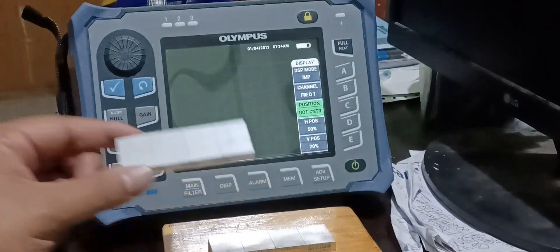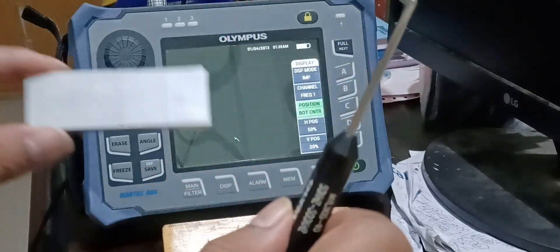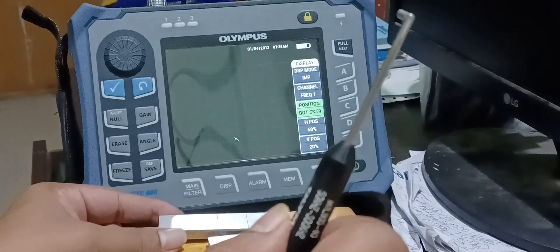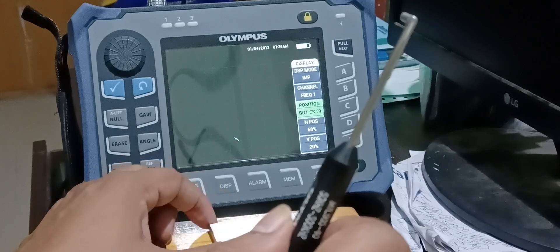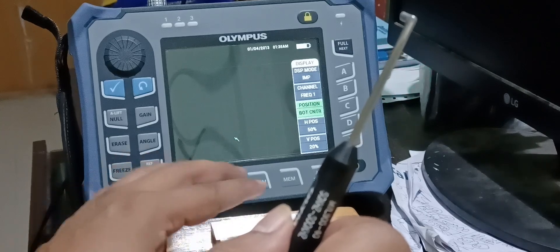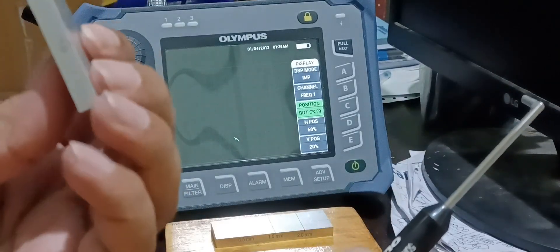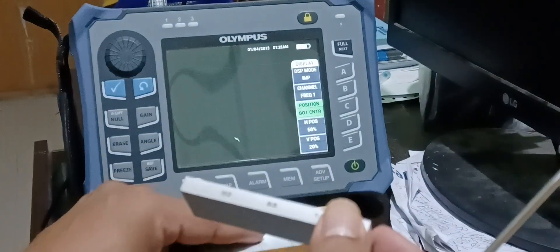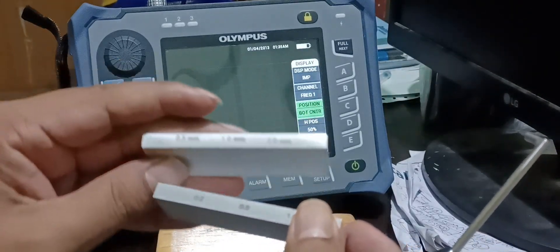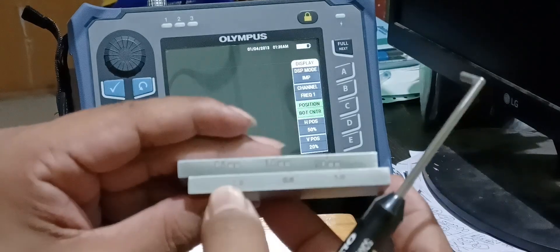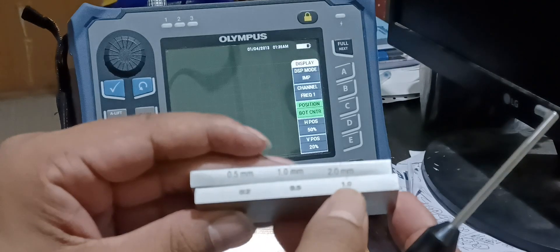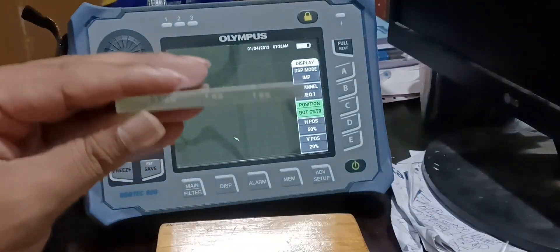Now, I will calibrate my probe and the signal with respect to this standard. And I will set the crack graph or the crack symbol as per this. Now, I have another standard. Same made of aluminum. But that is 0.2, 0.5 and 1 mm. And this is 0.5, 1 and 2 mm. This is 0.2, 0.5 and 1 mm. I will try to set up with this standard. Then I will try to catch up this crack.